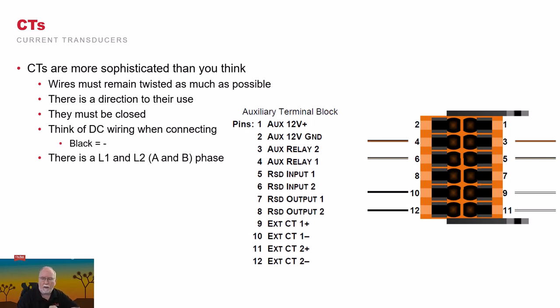CTs are L1 and L2 based. So you see here on the connector, there's an external CT 1 plus on 9, external CT 1 minus on 10, external CT 2 plus on 11, and external CT 2 minus. So it's very important. Think of DC wiring when you connect them up, so the black wire actually will be the negative, and there is again an L1 and L2 phase. If you're using from the grid, that'll show you a negative CT wattage. If you're selling to the grid, that'll show you a positive CT. And if you'd like to push loads, or load control, over to the main panel, you'll have to use CTs.